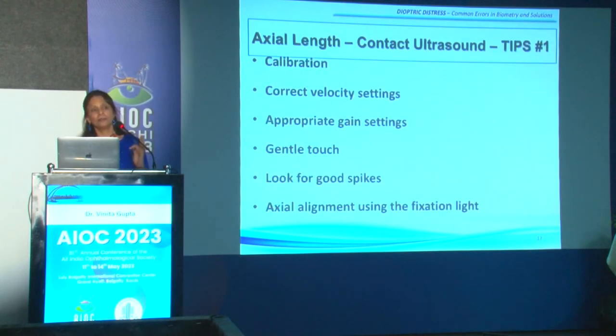Again, the tip for this is, please always calibrate your instruments, set the velocity settings correctly, and the gain settings appropriately. A very, very gentle touch if you're using a contact biometer, a contact probe. Ensure that there's no indentation happening, because that is a major source of error. Look for good spikes. What are good spikes? I'll just show you in the next diagrammatic representation of that.